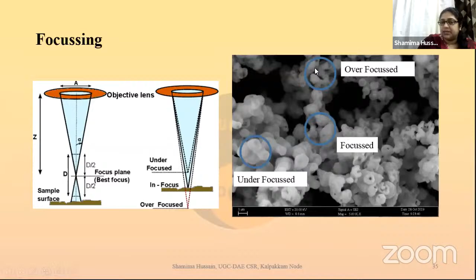Along with focusing, there is another thing called astigmatism, which is similar to what we have for our optical lenses. When the lens has this aberration, we will not have the focus at one particular point, we will have it at different points. So how does it look? If the focus is somewhere here, you might get images like this, whereas the actual image looks like this at the exact focus. The lens has some kind of aberration.